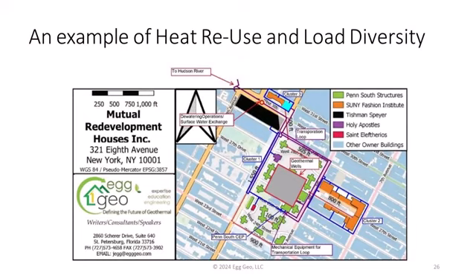So we said, if you let us pipe the energy right over here to this central energy plant, we'll replace one of those boilers with a 5 megawatt heat pump, and we will take all that energy, that 8 megawatts of energy, and use as much of it as we can to turn off the combustion heating. They have a hydronic, 4-pipe hydronic distribution system to all these buildings. So all we have to do is that at the central plant, and they've stopped all that combustion heating. Of course, we don't win them all by a long shot, but we won another award on that one because they said this is a great idea.